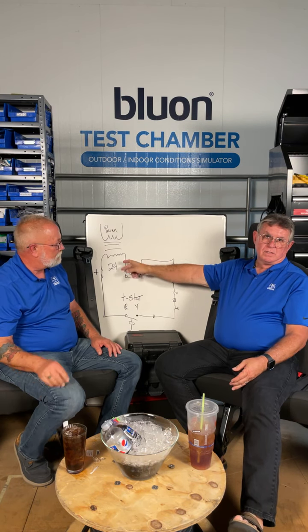Another thing that you're going to run into is grounding and bonding is critical, because you want to try to get a lot of that noise going to ground. And if you're using a shielded cable, do not connect the shield on both ends. No. You just create a big antenna. All right, you guys are all familiar with, I'm sure, the 60 hertz AC sine wave. So, I'm zooming in for this. If you run your low voltage wiring close to your high voltage wiring, this is where you start to pick up your noise, which is why they tell you not to run them in the same conduit. They should be separated by X amount of inches.